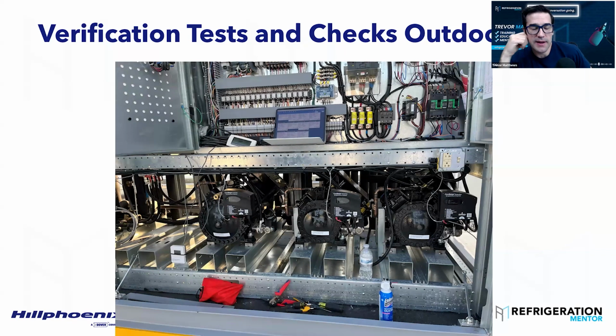How about I'll throw this one at you, Paul. Have you ever seen, because now we're doing high pressures, on our high side we're running 1200, 1300, 1400, 1500 PSI, 100 bar. We're used to just going into a 54-foot trailer, grabbing whatever copper pipe's there and putting it up. Have you ever seen where they put the wrong copper in the discharge line, because instead of high pressure copper, they're using K or ACR?